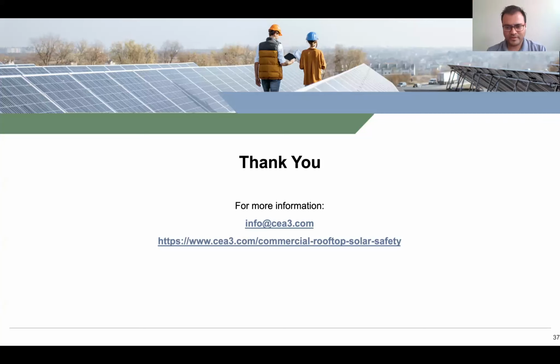Could you rephrase the question? Sure, just the type of connectors, is there a type of DC connector you would recommend or not recommend? All I'd say is whatever DC connectors you use, please follow the manufacturer's manual closely, and make sure your team is using the right tools while assembling the connectors. Most of all, use connectors from the same manufacturer for male and female. A lot of times we use RSD devices that come with their own connectors, so make sure the connectors in the rapid shutdown devices, optimizers, or microinverters are exactly the same as the modules, and your team is using exactly the same connectors on the DC home runs.